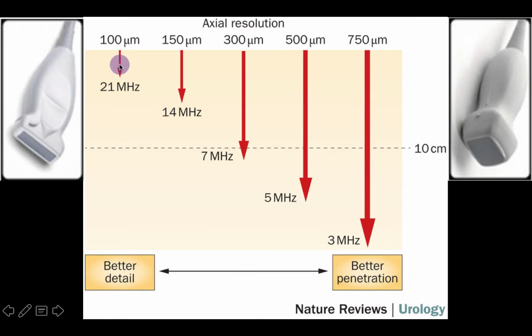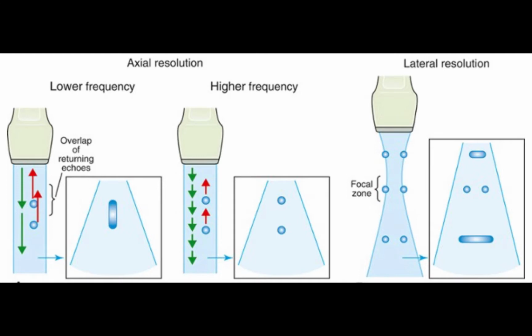Higher frequency ultrasounds penetrate less but generate higher quality images because of the better resolution they offer. This is the case for the linear transducer used for ultrasound-guided vascular access. Lower frequency ultrasounds penetrate deeper but generate less sharp images because of their lower resolution. This is necessary when you want to view structures deeper than about 5 centimeters.